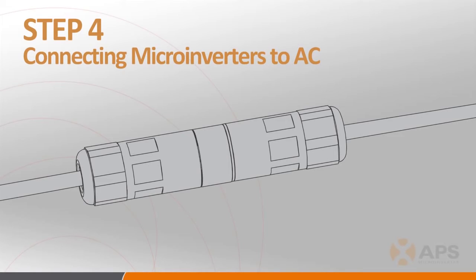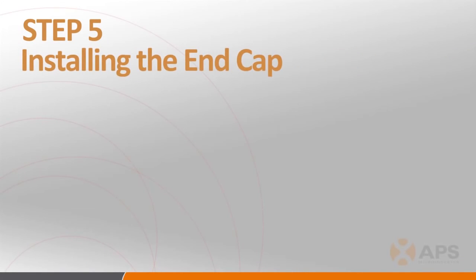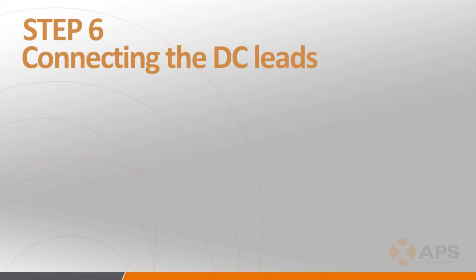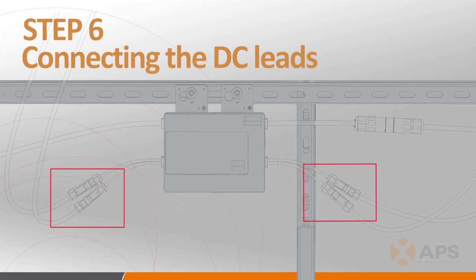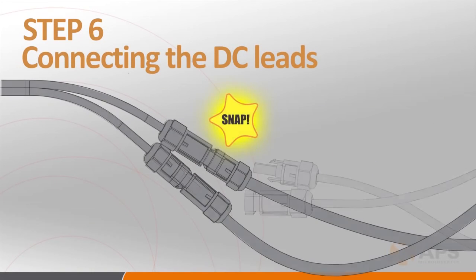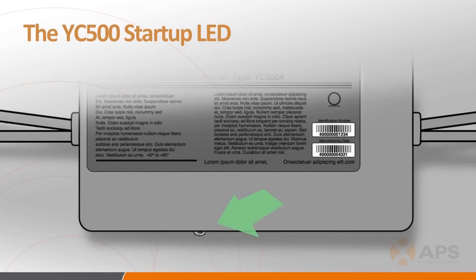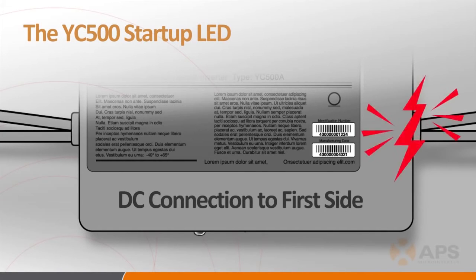Once the AC connections have been made, you're ready to move on to Step 5: installing the protective end cap onto the open AC connector on the last inverter in each branch circuit. Step 6: place the PV modules on the racking system and connect the DC leads from each of the PV panels to the microinverters, making sure that the connectors are securely snapped into place. The LED on the microinverter will flash green three times when DC power is first applied, indicating a successful connection. This startup indication only happens when DC power is applied to the first side of the connected inverter. Check the DC connectors if you don't see the green startup LED flash.